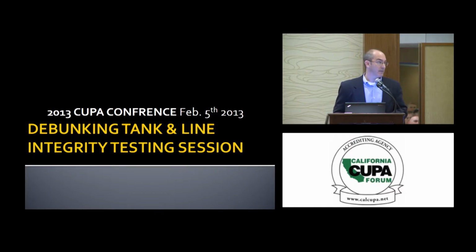Here's a graphical representation of the different ways that we could detect a hole in a tank. If there's a hole in a tank that's just buried in fill without any water around it, it will draw in an air bubble, and that will cause a very readily discernible acoustic signal. If there's a hole in a tank above the product level, it will cause a different type of audible sound in the tank, and it tends to cause a loss in vacuum as well. Although that's not part of our third-party certification, that's something that our software accounts for.